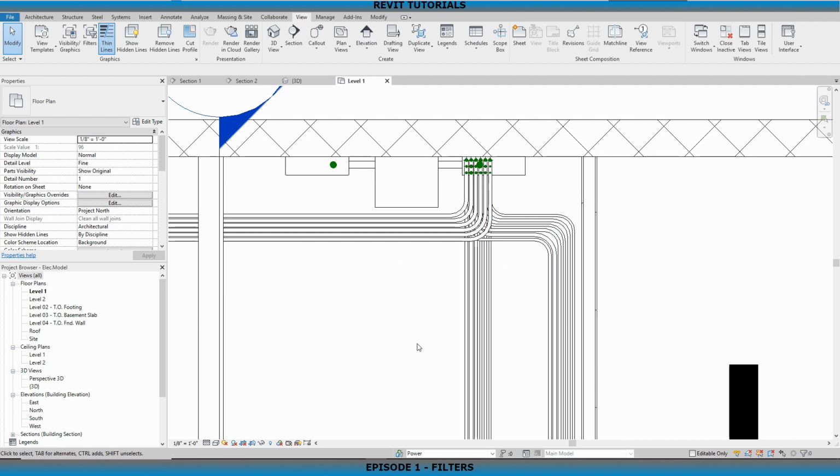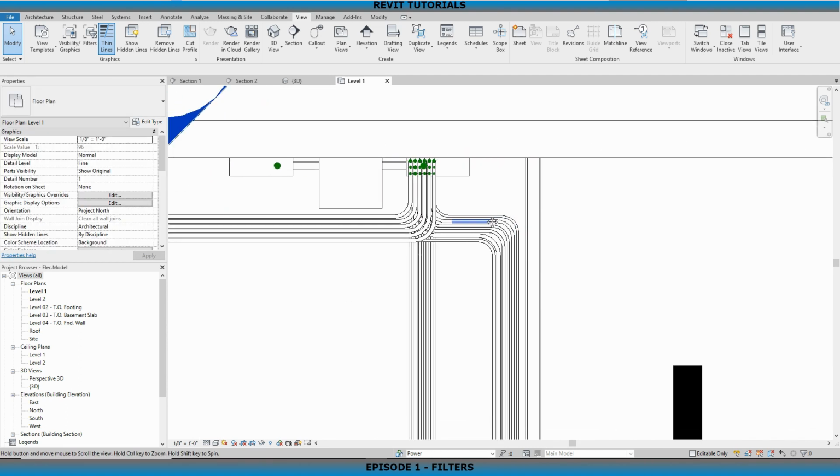This replaces the need to create a separate work set and then put all of your conduits on panel A onto that work set and all your conduits for panel B on that work set, which over time you get a lot of work sets, and that creates a lot of confusion. They get misused, they add a lot of space to the project. So this is the very nice and lightweight way of taking and removing stuff from visibility in your view.